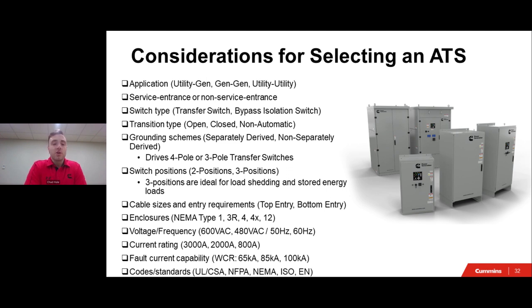Also, it is important to take into consideration your grounding scheme, as this could play a huge factor in whether or not you're using a three-pole or four-pole transfer switch. Cable sizing and conduit entry is also an extremely important topic. Do you have the right number of cables? Do you have the right size of cables? And are these cables coming from the top, bottom, or other entry points of the transfer switch, as those could affect how your transfer switch is placed within your system?